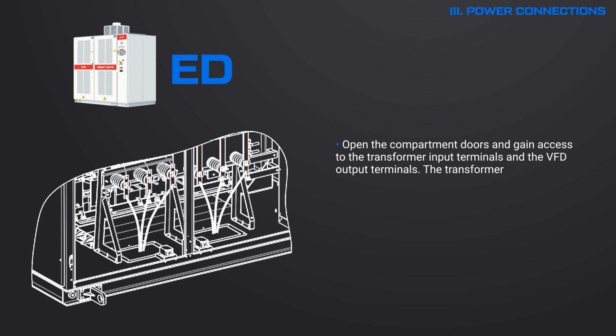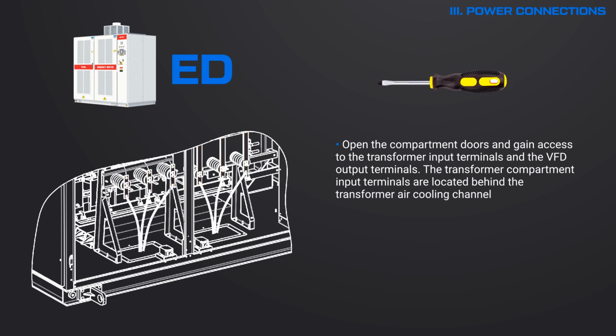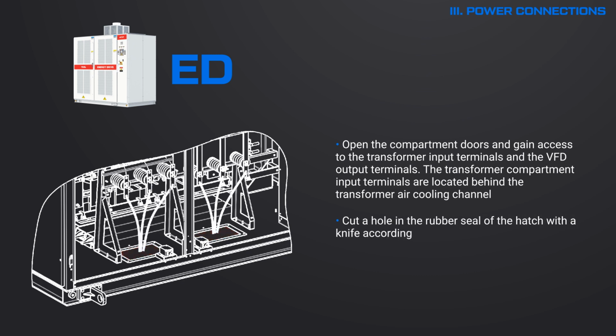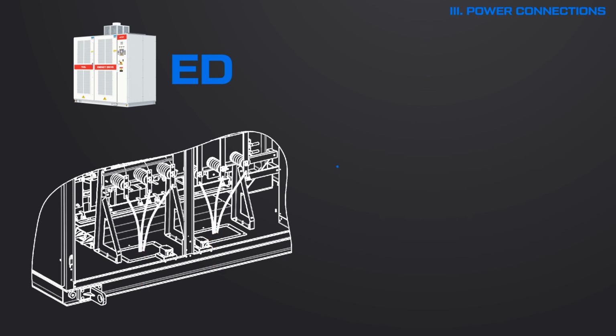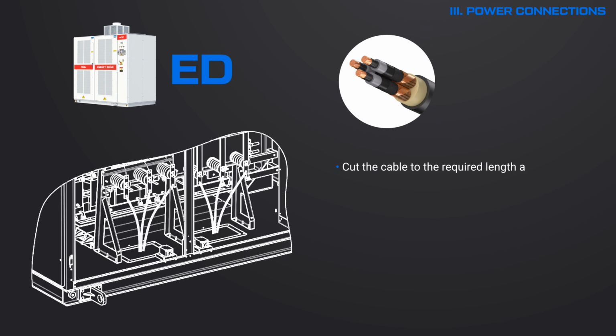terminals. The transformer compartment input terminals are located behind the transformer air cooling channel. To access the terminals, remove the cable cover by loosening the polyamide screws with a PH2 screwdriver. Cut a hole in the rubber seal of the hatch with a knife according to the cable diameter. Seal the cable and pass the cable through the hole. Cut the cable to the required length according to the requirements for the preparation, laying, and connection of cables.